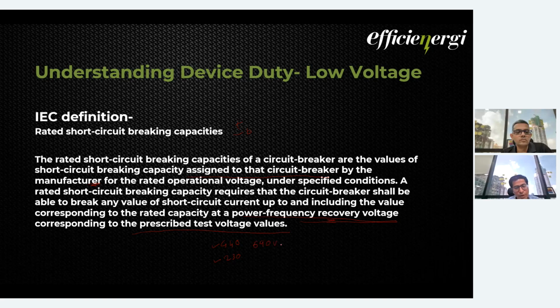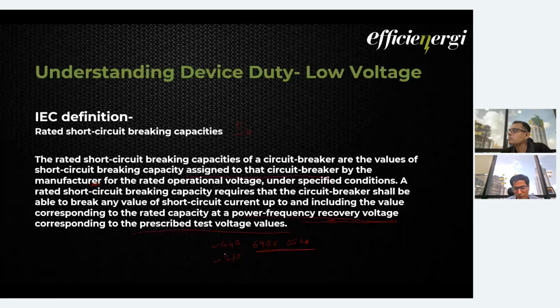So 690 volts, 55 kiloampere, this kind of combination you can also see. That again depends on the test bench that the particular lab has. So they can have a different voltage, and the manufacturer has to give the value for those particular voltage levels.